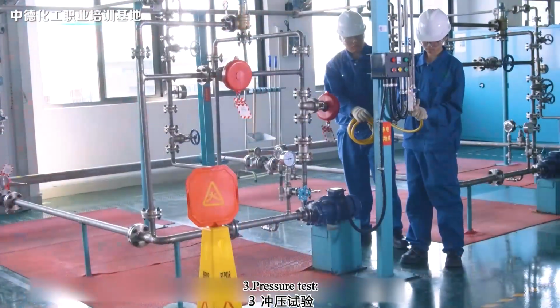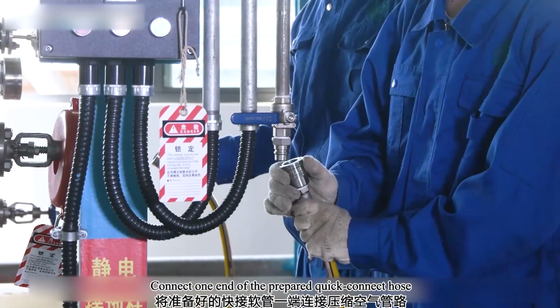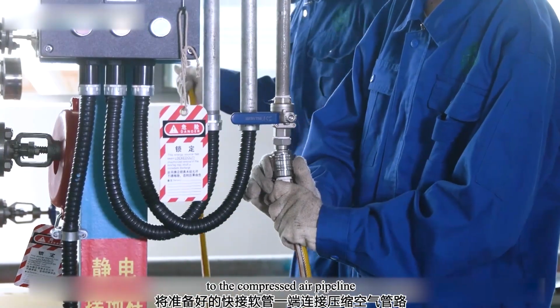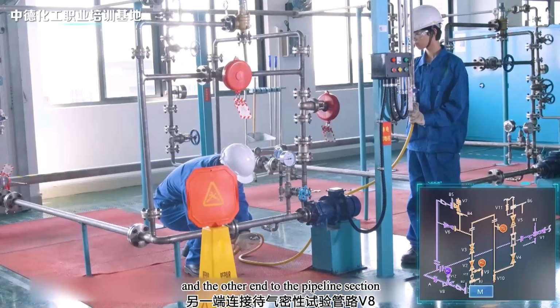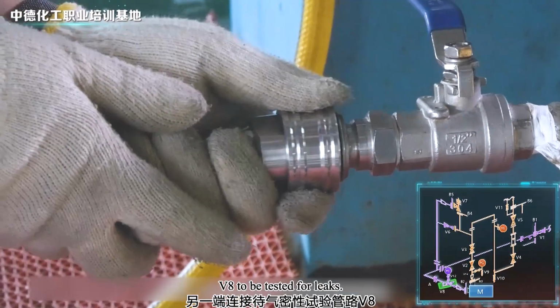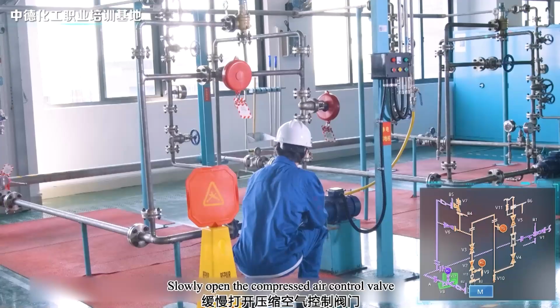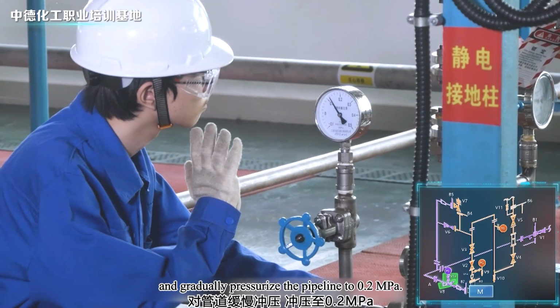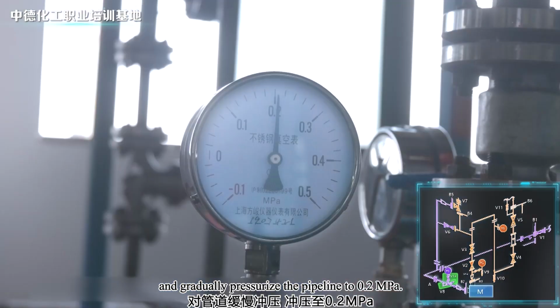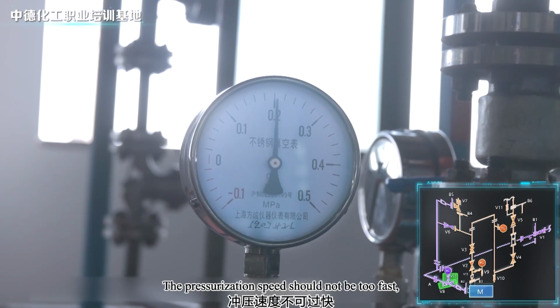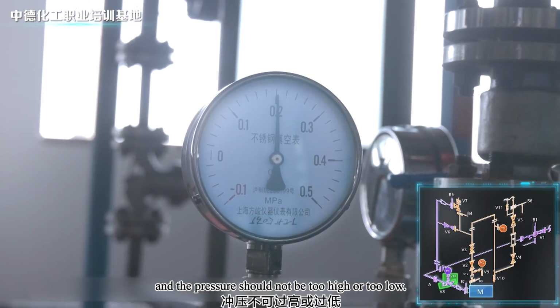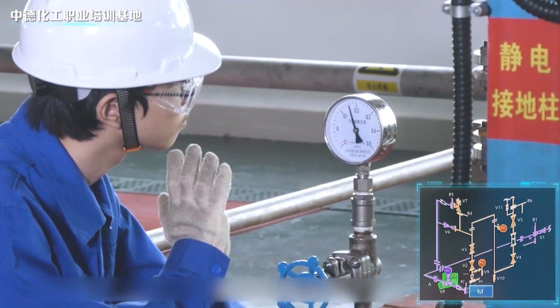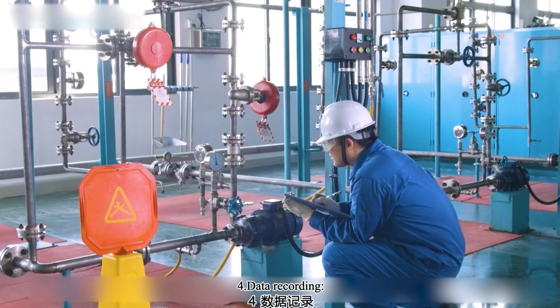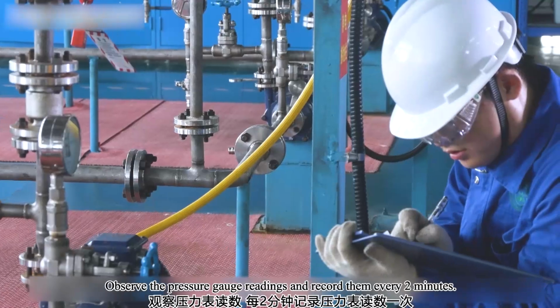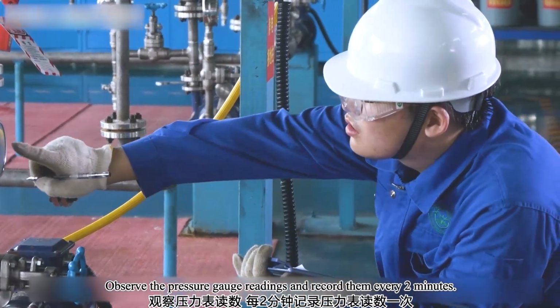Third, pressure test. Connect one end of the prepared quick connect hose to the compressed air pipeline and the other end to the pipeline section V8 to be tested for leaks. Slowly open the compressed air control valve and gradually pressurize the pipeline to 0.2 megapascal. The pressurization speed should not be too fast, and the pressure should not be too high or too low. Fourth, data recording. Observe the pressure gauge readings and record them every 2 minutes.